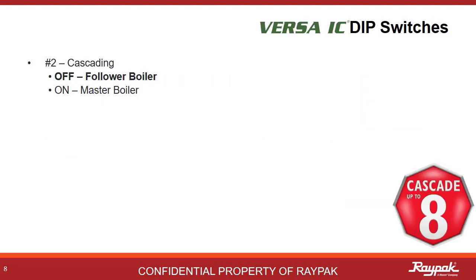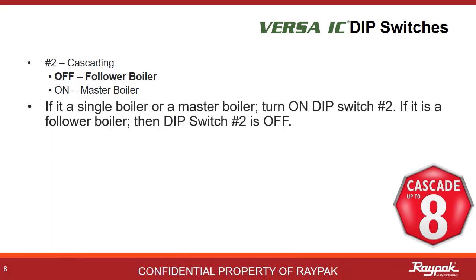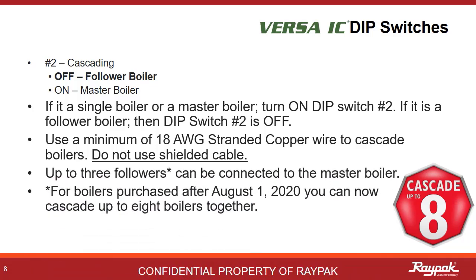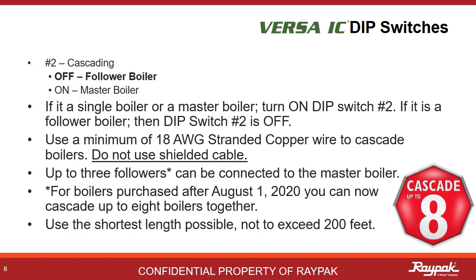Dipswitch number two tells the boiler if it is a master or a follower. When there is only one boiler, it is always a master. In cascade systems, there can be only one master. Always use 18 gauge stranded copper wire for cascade communications. Only use non-shielded cable. You can now connect up to seven followers to the master for an eight boiler cascade. Use the shortest possible run, not to exceed 200 feet.